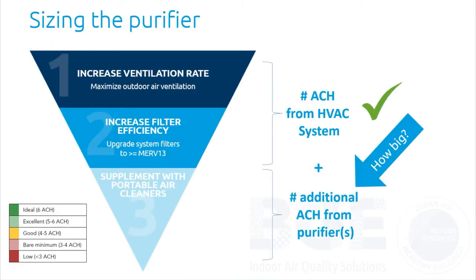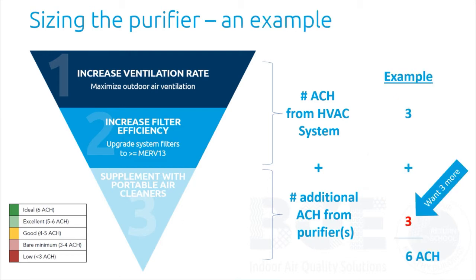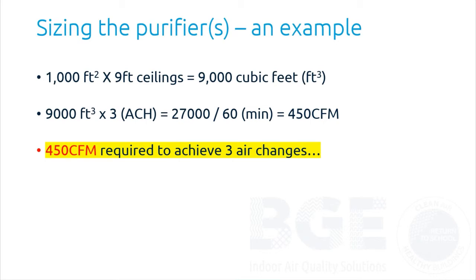So we've got the air changes per hour. We figured it out from one of the methods I talked about. How big a unit do we need, or how many do we need? For the example we have, we're going to start with the ones that were red, the 3s. So we have 3 air changes there, and we need an additional 3 air changes from the CADR from the units. Here's a quick example, just to show how you would go about that.